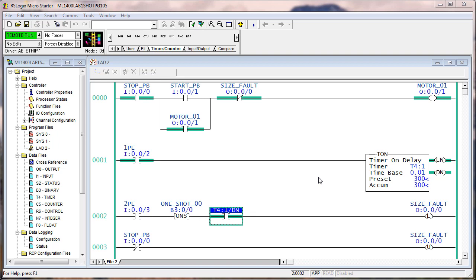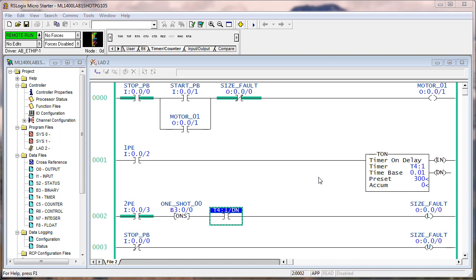Now if you hit 2PE then you get a size fault. You'll clear 1PE eventually and then 2PE, and 2PE is not going to clear until you start the motor again. So right now we have a size fault. If we push stop, that resets the size fault — but 2PE is still blocked. So if I turn on start, the conveyor starts moving and eventually 2PE clears. Now if somebody were to come up and flash 1PE with their fingers, it's not going to make any difference unless it goes the full three seconds. So you can see that although this is not perfect, it is an improvement on just using the one-shot.